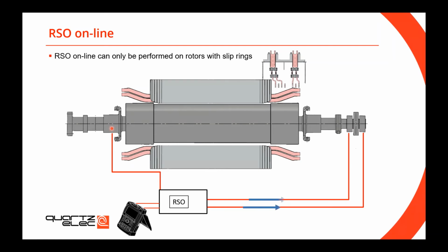It's that simple. It will take 15 minutes, maybe half an hour, and you have your online reading at 3000 RPM with centrifugal force acting. So if you have problems, this will reveal them. It's a good tool. Remember maybe to incorporate that test in your future maintenance activities.